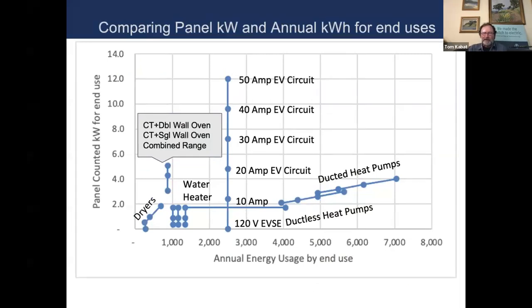This is just a little plot that differentiates on the bottom axis the annual energy use by the different end uses, and on the vertical axis, the panel-counted kilowatts for each end use. You can see a difference here between the different end uses and approaches I've been talking about. Look at the car chargers: for going, say, 15,000 miles a year, the annual energy is the same no matter what circuit size you pick, but the number of amps counted in your project, for whether you have space to electrify everything or not, is really different based on what size circuit you pick.